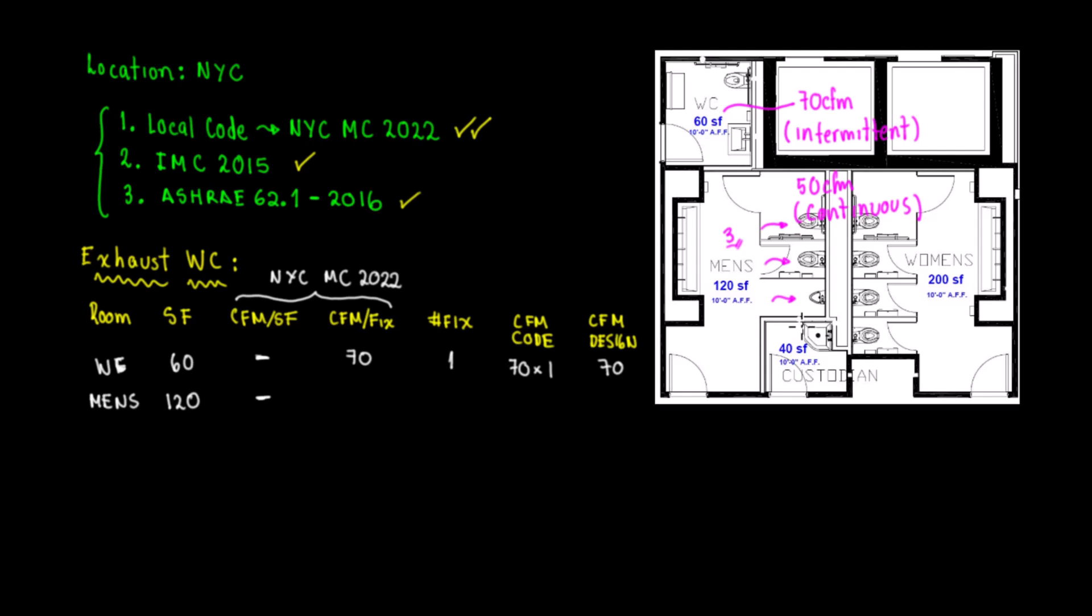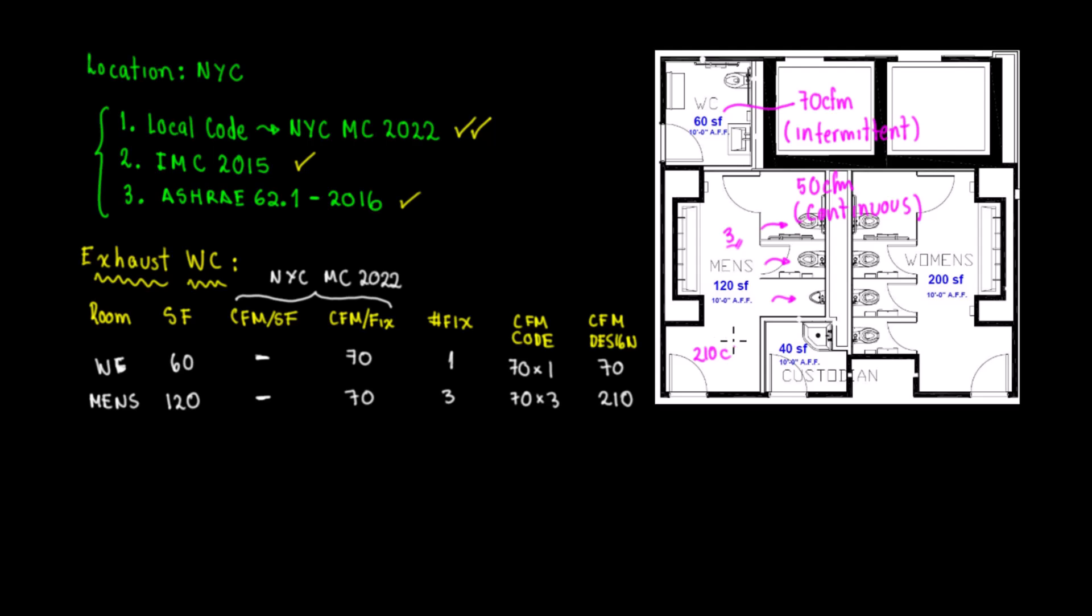By code we determine that the CFM per fixture is 70. Number of fixtures is three, so we have 70 times 3, and the design CFM would be 210. For this space what we need is 210 CFM of exhaust. Remember this exhaust means intermittent because if it wasn't intermittent it would be 50 times 3, 150 CFM running all the time when there's people there.